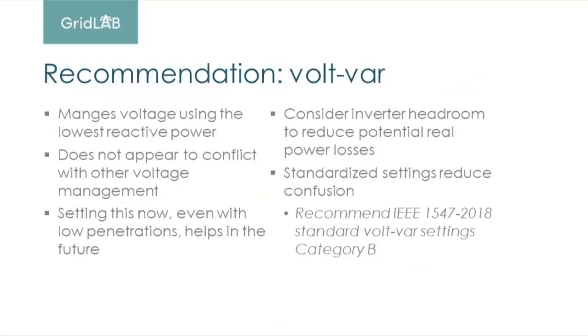So our recommendation, surprise, surprise, is that volt-VAR is the preferred voltage regulation mode. We think it manages voltage using the least amount of reactive power. We don't see that it conflicts with other forms of voltage management.